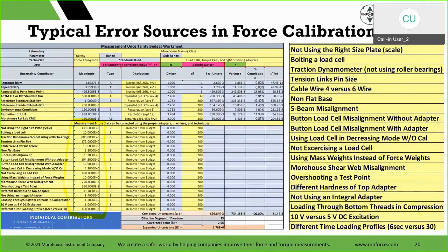things you can control, right? Not using the right size scale plate, you can control that. You can buy the right size plate. Bolting a load cell, that's some torque specification. Traction dynamometer in the cal machine: this one really needs special adapters because the error is about 8%. If you take off those shackles and put them in the cal machine, and we do have adapters with pressed-in bearings, but you don't use those bearings, 8% error.